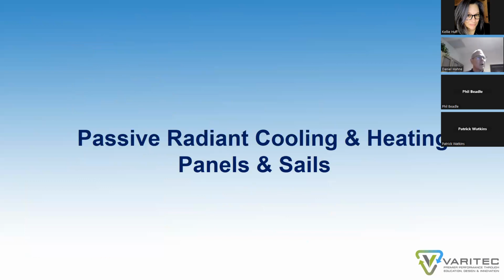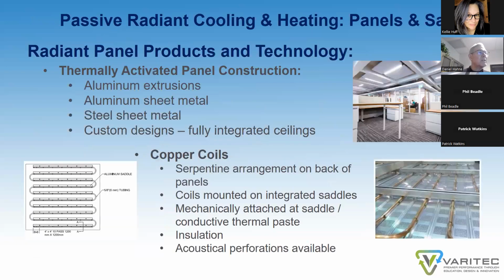And then, of course, you want to have VAV control for zones that see wide swings of occupancy within that space. So passive radiant cooling and heating panels and sails, what are these devices? Well, these are, again, thermally activated panels or louvered sails that reside in the ceiling, or possibly for panels in a wall, that are thermally activated. They are made out of aluminum extrusions, especially for sails, and aluminum sheet metal for panels. They can be made out of steel, and they can be made in custom configurations. Along the back of these sheet metal pans or louvered sails are serpentine coils that are placed and adhered on saddles with thermally conductive paste or adhesive, so that we maximize the heat from the coil through to the surface of the panel. Another thing to keep in mind is the acoustical performance of the panel and whether or not they need to have supplemental insulation on the back to maintain adequate sound within a space.